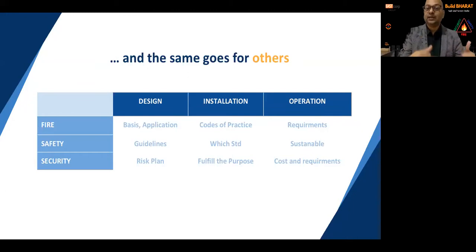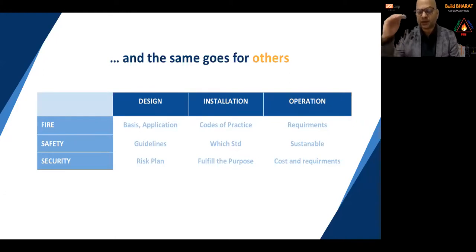And that's how you fail to involve yourself in understanding the code interpretation, and that's how the failure gets started. Installation codes of practice - what is it? When code talks about 1.2 meter maximum height for an MCP or an extinguisher, there is specific meaning to it. Unless you know the purpose and meaning of it, you will not prevent a contractor from installing it at a height more than 1.2 meters. So you must understand your installation standard when it comes to fire and life safety.